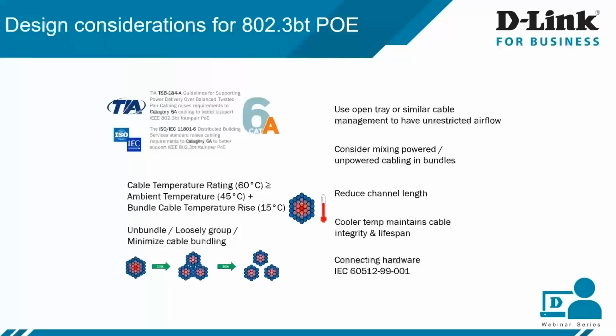So what are the precautionary points to avoid this? There are some measures which we can take. We can ensure that the ambient temperature and the cable bundle temperature do not exceed the cable operating temperature. Minimize the cable bundling. Use the guideline. If possible, use open tray or similar cable management to have unrestricted airflow. This is very, very important. Reduce channel length.